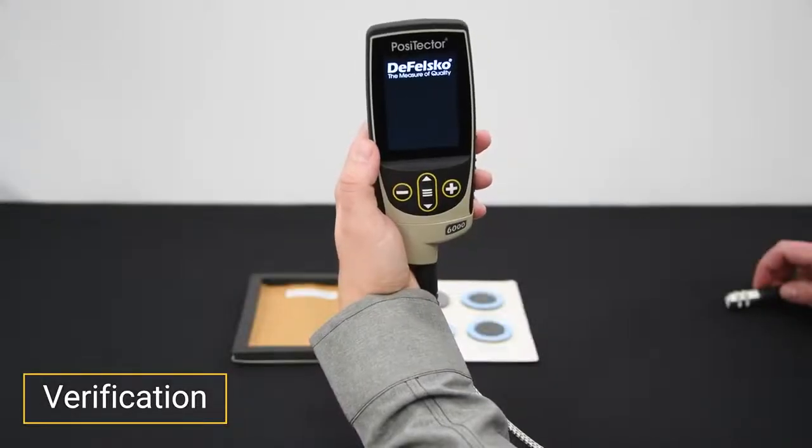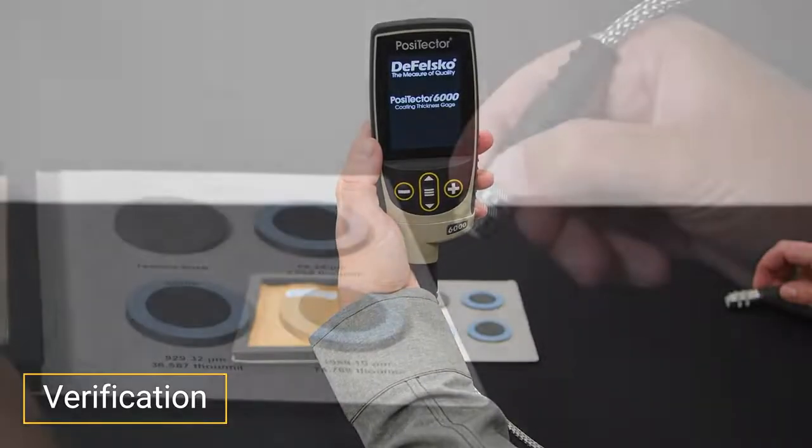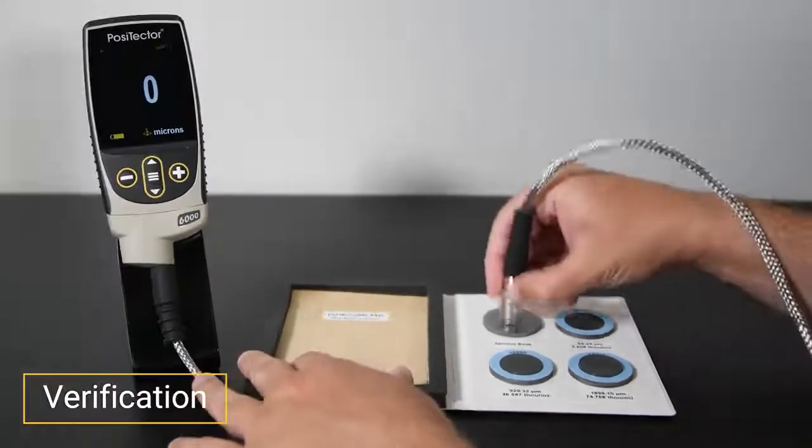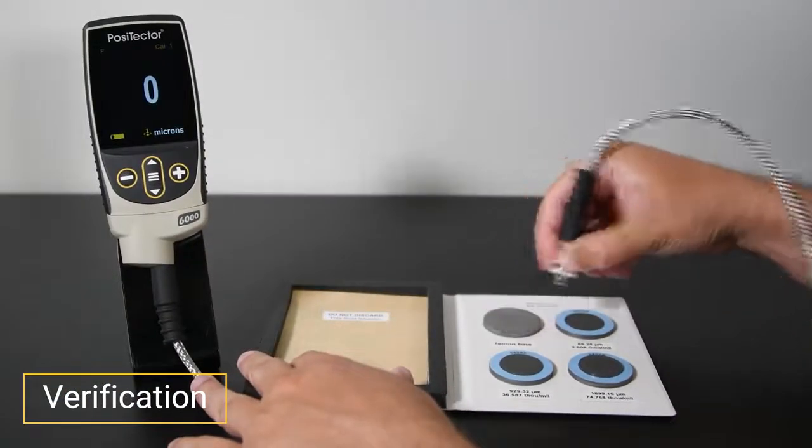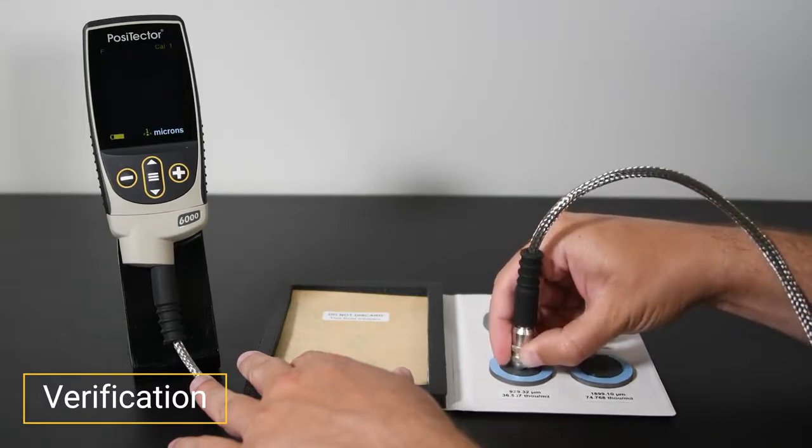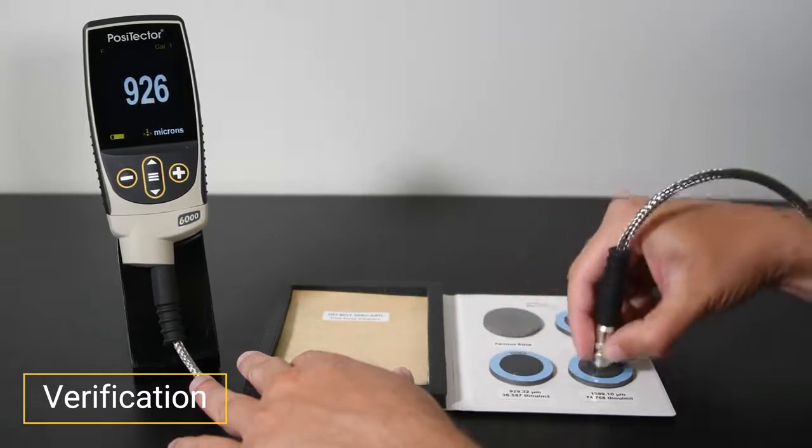Power the gauge on with the center navigation button. Hold the instrument near the probe by the outer shell or probe casing, not the cable. Simply take measurements on certified coating thickness standards and ensure that the instrument is measuring within the combined tolerance of both the standard and instrument.